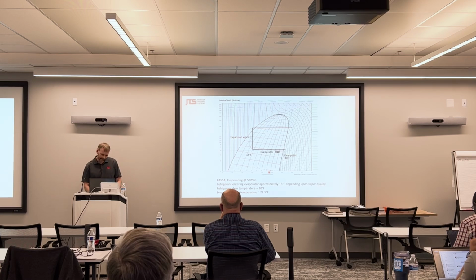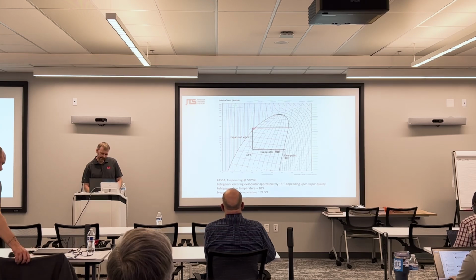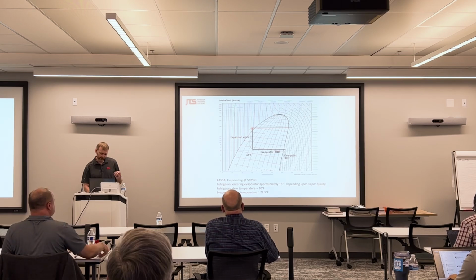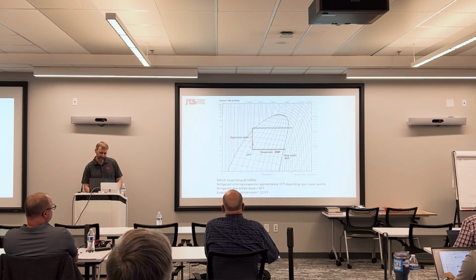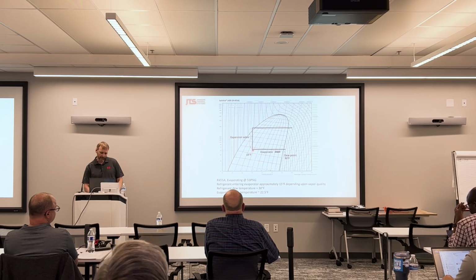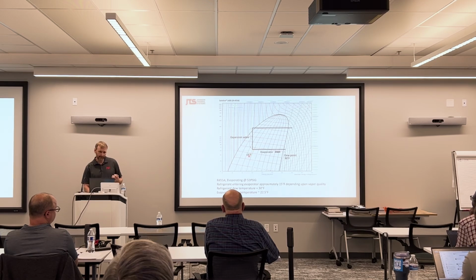So next, let's talk about what happens going through the expansion valve. Based upon your condensing temperature and the amount of liquid subcooling, your liquid line would then enter the expansion valve, which expands the refrigerant. As it expands the refrigerant, we start generating a mixture of liquid and vapor. What enters the evaporator coil is very dependent upon where you're condensing and what your liquid temperature is before condensing. But generally speaking, you're entering at a vapor quality somewhere between 0.25 and 0.5, so somewhere in this area. Based upon whatever your vapor quality is determines the temperature of the refrigerant at the very inlet of the evaporator. So in this example, it might be 15 degrees at the very first pass of the evaporator coil.